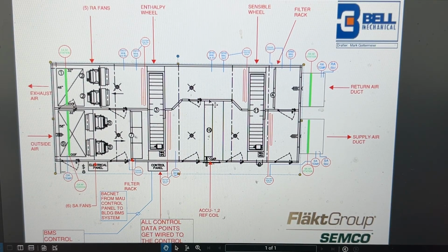So quickly, I think the most important thing to talk about is the two wheels here. We've got the enthalpy wheel and the sensible wheel. The sensible wheel is transferring sensible energy, or thermal energy only, between the exhaust and makeup air streams. The enthalpy wheel transfers both sensible and latent energy. So it adsorbs and releases water vapor as it rotates between air streams, enabling moisture transfer as well as temperature transfer. And I guess that makes it effective for humidity control. So those are the two most important in my opinion, on how we're reclaiming some of that exhausted air to help treat the incoming air serving the building.